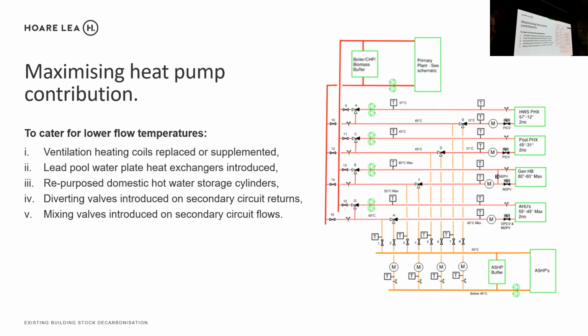We introduced lead plate heat exchangers onto the pool water plate heat exchangers so they could do as much work as possible before the boilers did the rest. To achieve that, we fitted diverter valves on the return circuits, whether the ventilation circuit, the pool water plate heat exchanger circuit, or the space temperature heating circuit.